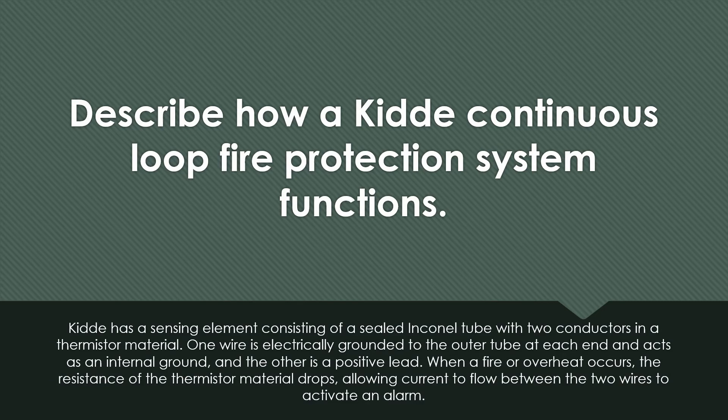Describe how a Kidde continuous loop fire protection system functions. Kidde has a sensing element consisting of a sealed Inconel tube with two conductors and a thermistor material. One wire is electrically grounded to the outer tube at each end and acts as an internal ground. The other is a positive lead. When a fire or overheat occurs, the resistance in the thermistor material drops, allowing current to flow between the two wires to activate an alarm.